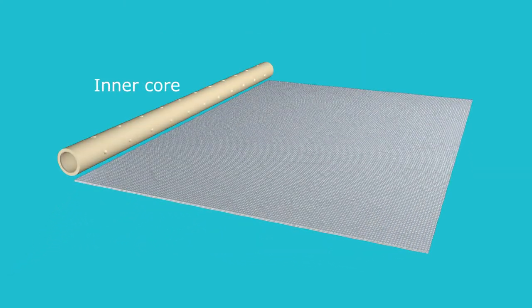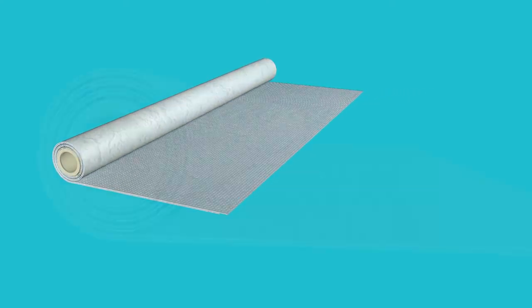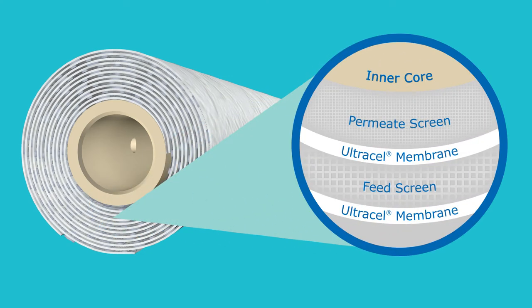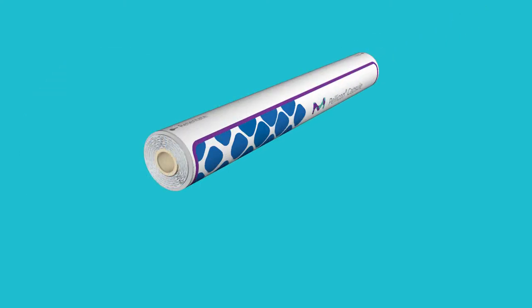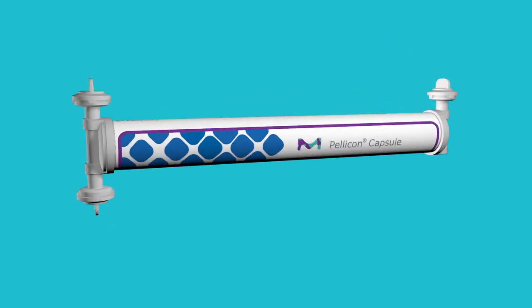The layers are then wound onto a hollow, perforated inner core. The wound assembly is then potted to form a filtration element that is then inserted into a cylindrical housing. End caps containing the ports are then bonded to the housing, forming the Pellicon Capsule.